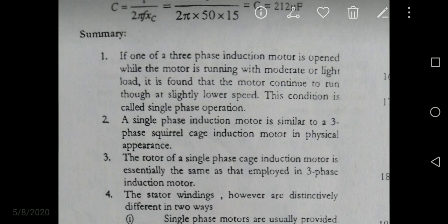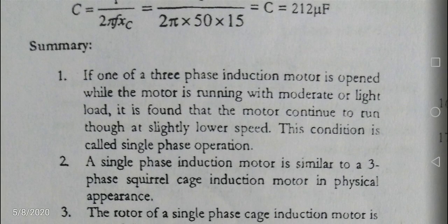So the next topic is a summary of this. If one of the phases of a three-phase induction motor is opened while the motor is running with moderate or light load, it is found that the motor continues to run at slightly lower speed.